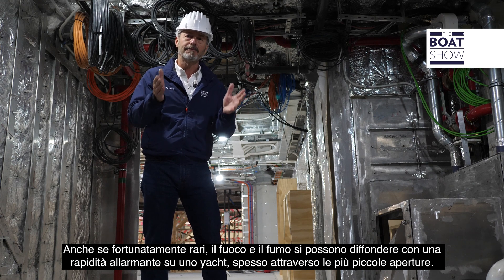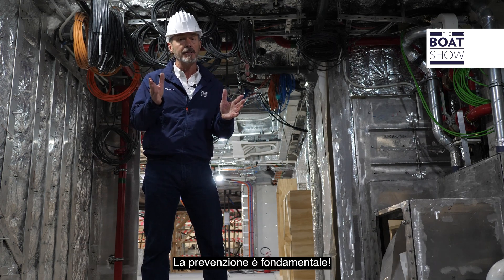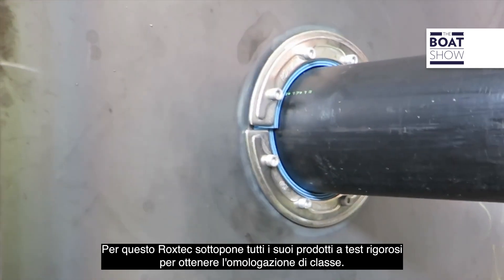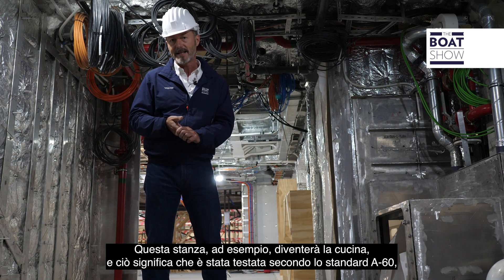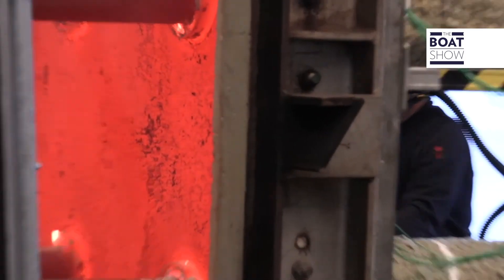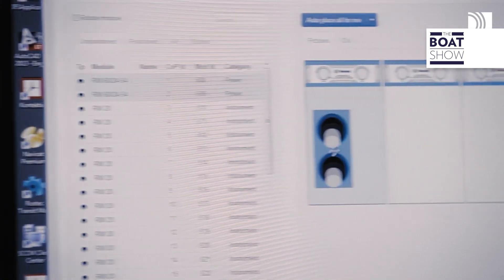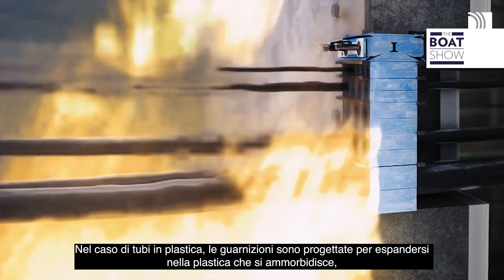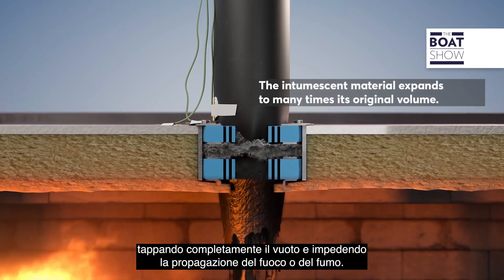Although thankfully rare, fire and smoke can spread alarmingly quickly on a yacht, often through the smallest of openings. Prevention is obviously crucial, and so Roxtec aggressively tests all its products to meet class approval. This room, for example, will eventually be the galley, and that means it's tested to A60 standard — equivalent to one hour's fire stop at 180 degrees centigrade. In the case of plastic pipes, the seals are designed to expand into the softening plastic, plugging the void completely and preventing fire and smoke from spreading.